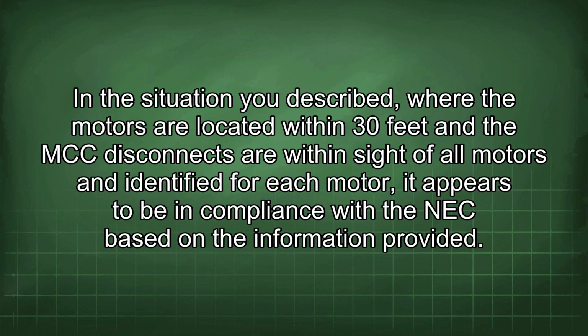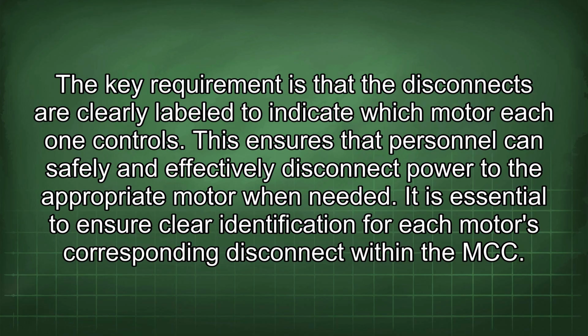In the situation you described, where the motors are located within 30 feet and the MCC disconnects are within sight of all motors and identified for each motor, it appears to be in compliance with the NEC based on the information provided. The key requirement is that the disconnects are clearly labeled to indicate which motor each one controls. This ensures that personnel can safely and effectively disconnect power to the appropriate motor when needed.